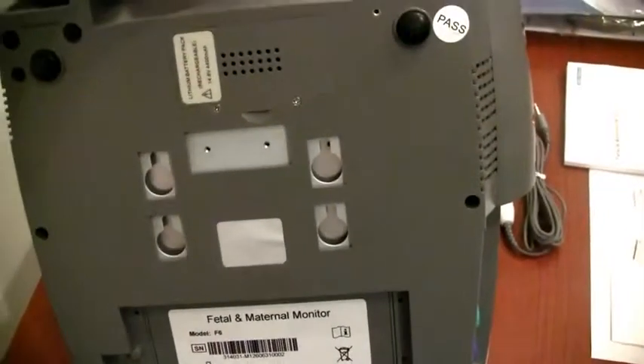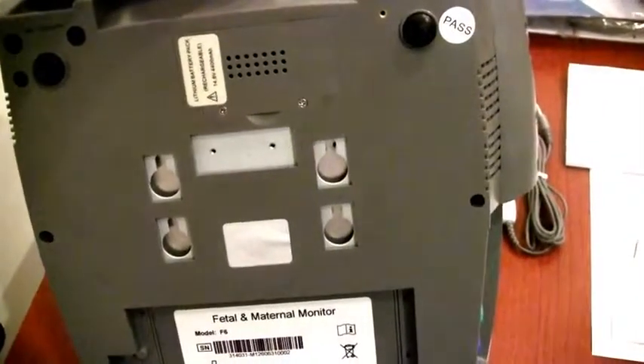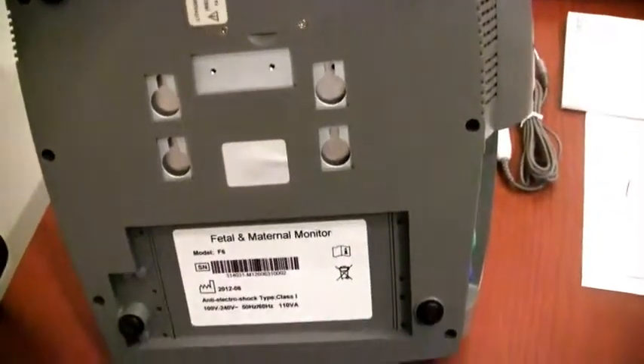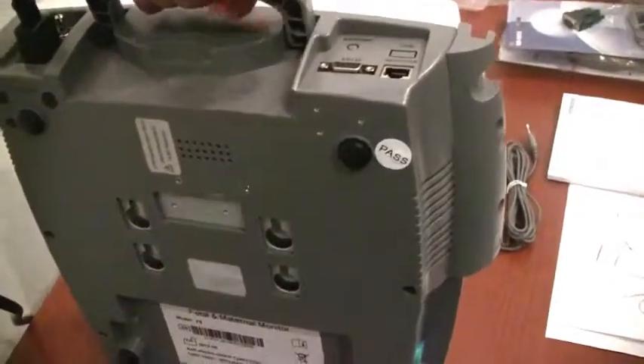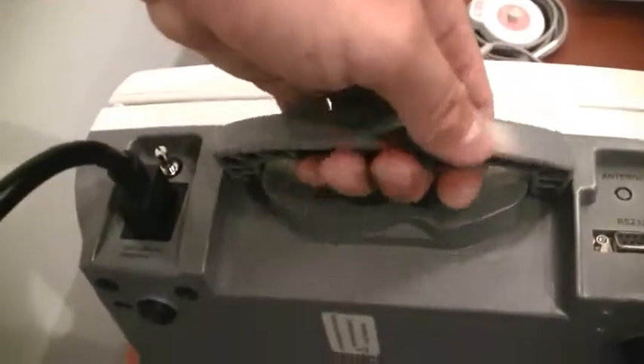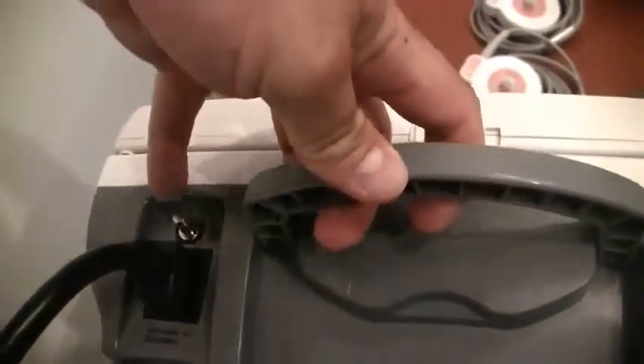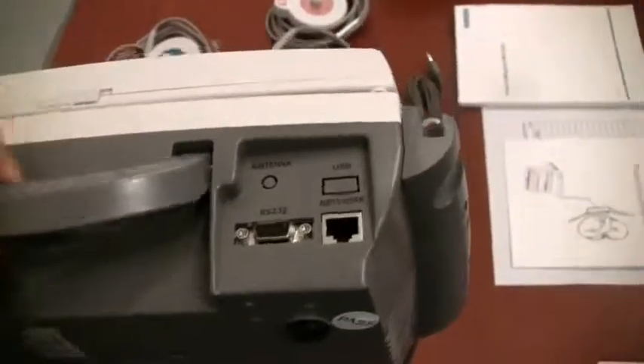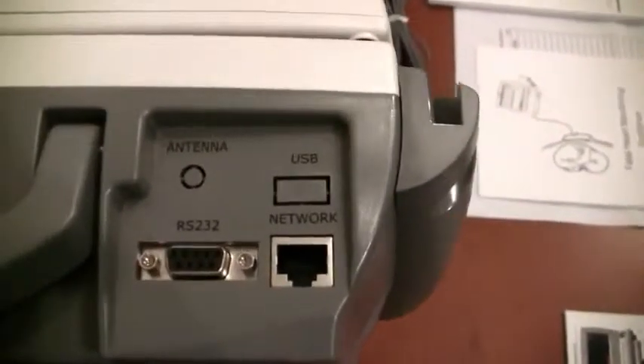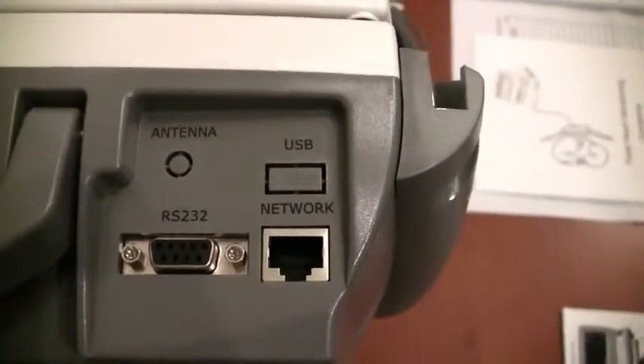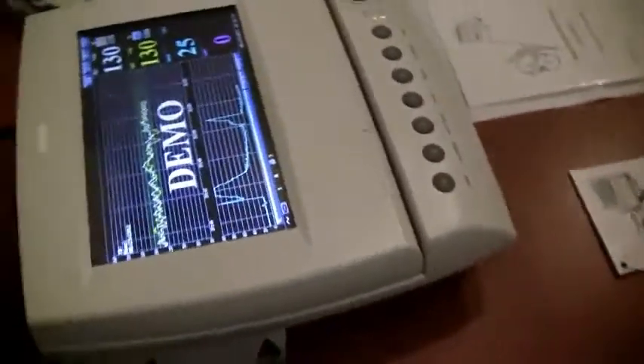On the back of the unit, you'll see there are connections to have it on a wall mount, either a flush wall mount or a pivot wall mount. It can also be put on a trolley. You've got your power source on the back here, your ground if need be. There's your RS-232 port and your network port for the Ethernet connection. Put the unit back on its side here.